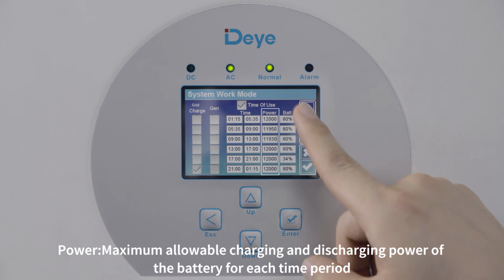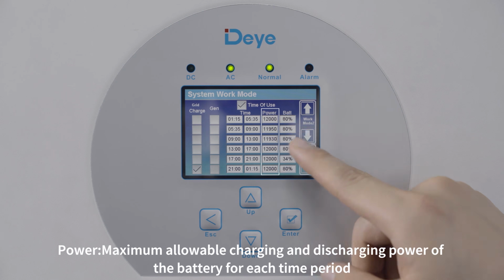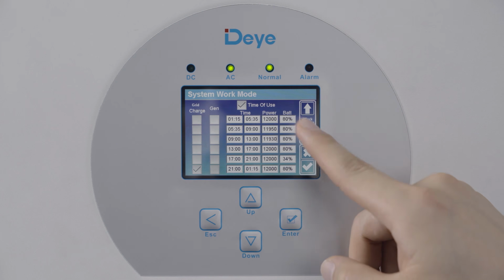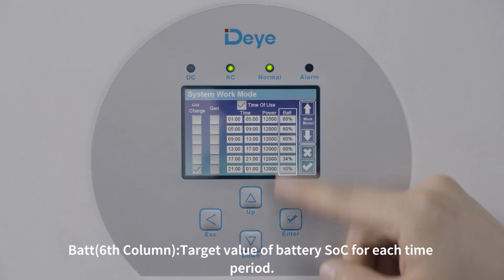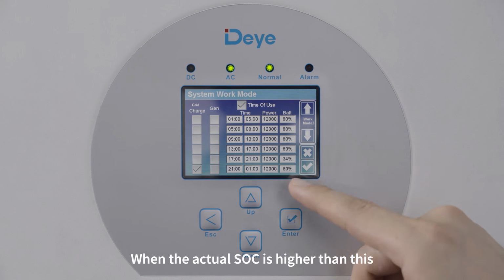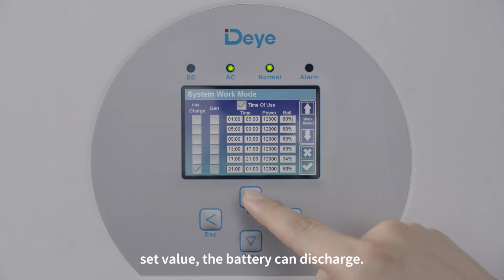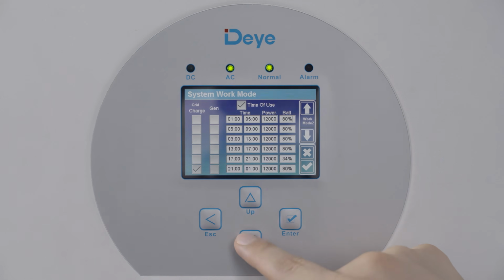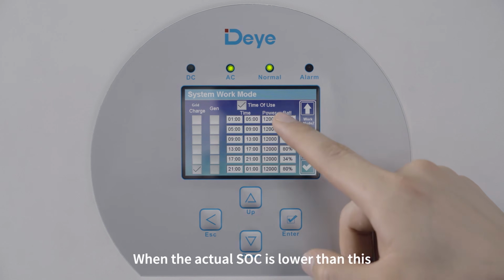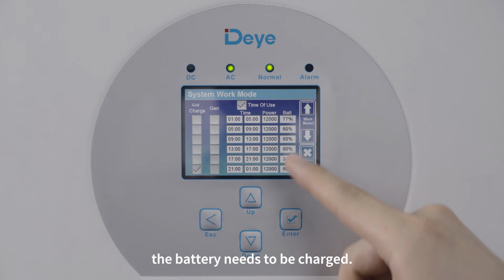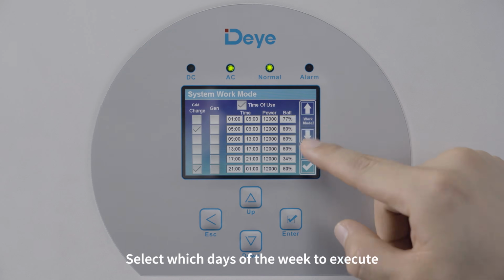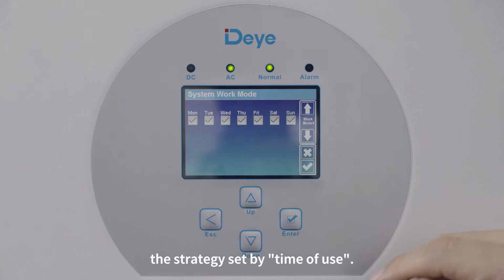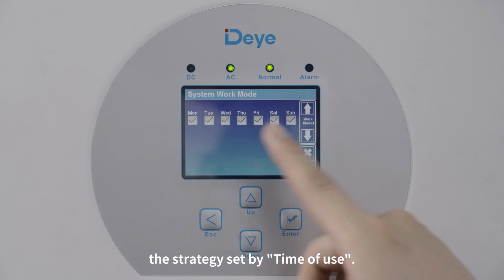Power: the maximum allowable charging and discharging power of the battery for each time period. BAT, 6th column: the target value of battery SOC for each time period. When the actual SOC is higher than this set value, the battery can discharge. When the actual SOC is lower than this set value, the battery needs to be charged. Select which days of the week to execute the strategy set by time of use.